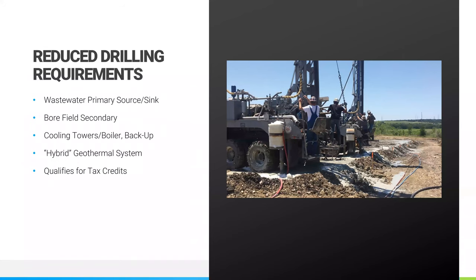So going back to reducing the drilling requirements when we're using wastewater as the primary source and sink, that bore field becomes your secondary. So it's a whole lot less incremental first cost, while achieving similar and possibly better results from the entire system itself. And one benefit to the owner of that loop field is it is also considered a hybrid geothermal system.